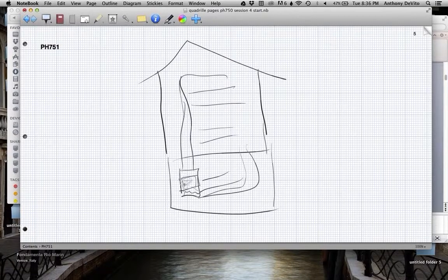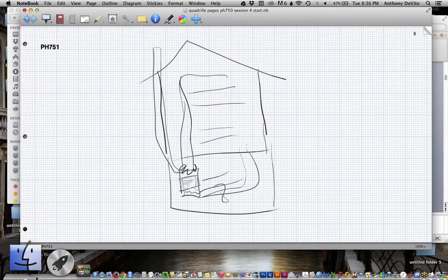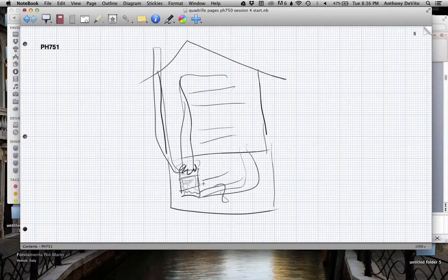Well, there's a furnace in there with a little, like a heat exchanger. The fire goes on one side, and then there's a smokestack, goes out the smokestack, so you don't poison everybody in the house. And the air from the house goes on the other side. You got a fan. Well, what they'll do very frequently is they will put a Freon coil in here. And that Freon coil, in the summertime, the burner goes off. You're not heating. And you use that Freon coil, you blow air over that Freon coil to cool the air and to condense the air, right?